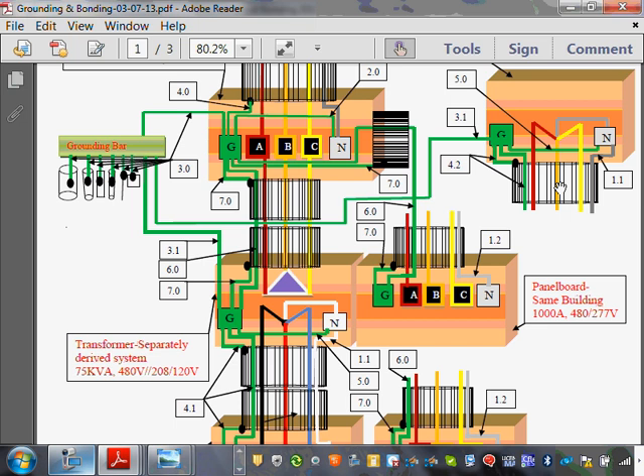When you get a bigger one, like 1250 kW, that's a big boy. These are typically in a room in an enclosure and tied to the grounding electrode system. And when we design them, we go even bigger. Engineering-wise, we go bigger than number 6 to the ground at that size.